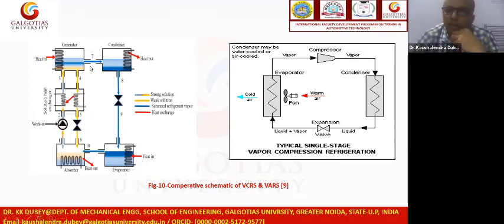So the mechanical compressor is replaced by the generator. The two main functions of the compressor are to increase the temperature and to increase the pressure. For the temperature increment, we have the generator, which runs by the engine exhaust. This generator can directly take the energy from the engine exhaust source as per the size and as per the cooling load. All these design things depend on our cooling load, whatever is required: 1 ton, 2 ton, 3 ton, 5 ton, and so on. Temperature can be increased by the generator, and the pressure is available from the pump. Here the refrigerant pump is available. So these two things can replace the mechanical compressor of the VCR system. The pump pumps the liquid.